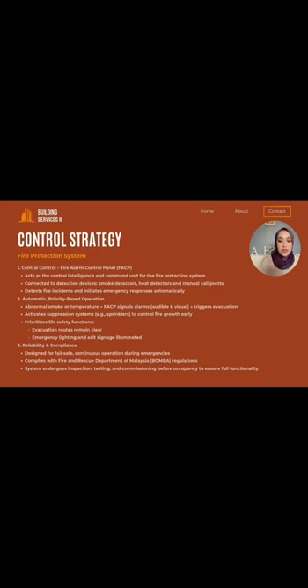Next is automatic and priority-based operation. Abnormal smoke or temperature will signal the FACP to trigger evacuation. It will activate the suppression system, such as sprinklers, to control fire growth early. It prioritizes life safety functions: evacuation routes remain clear, and emergency lighting and exit signage are illuminated.